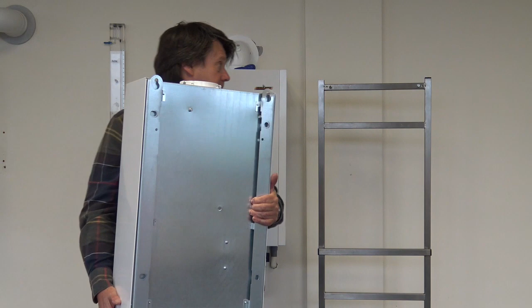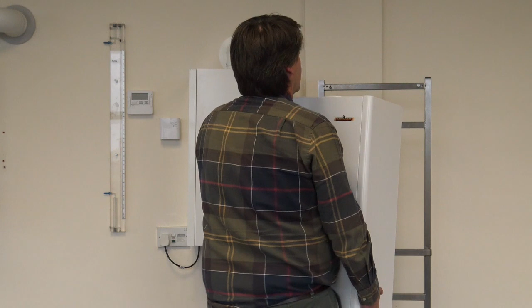That's the boiler frame. Imagine those two coach bolts in the wall. Put your template on the wall, mark for the top fixings, not necessarily the bottom fixings due to the weight of the boiler. Offer the boiler up onto your first fixing, it's safe, swing around, hang on the second fixing. No brackets over the back, nothing you can't see when hanging the boiler. The coach bolts are seen, the lugs are at the top, and on the customer's eye line they can't see those fixings. Right, let's look at the fluing system.